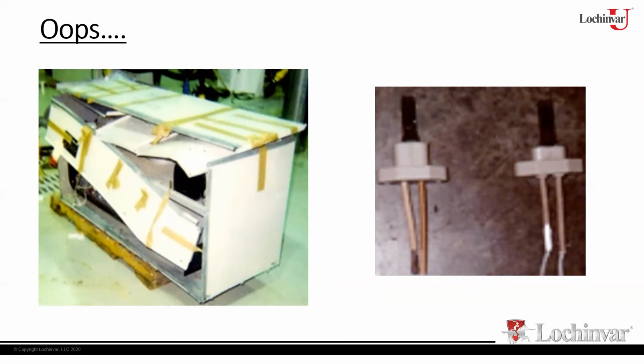Unfortunately for this gentleman, he kept resetting it immediately. After about the fourth or fifth time, the igniter finally caught. And when it did, we had this chamber full of gas and air, and it lit off. And unfortunately, this was the end result. So when you're talking about hot surface igniters, you do want to be very careful and make sure that you're using the correct igniter. There are a lot of igniters out there. Some of them will look a lot alike, but they all have different amp draw to temperature characteristics. So you have to keep that in mind. Make sure you grab the right one, okay?